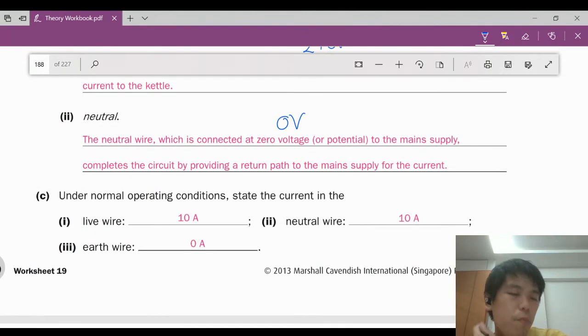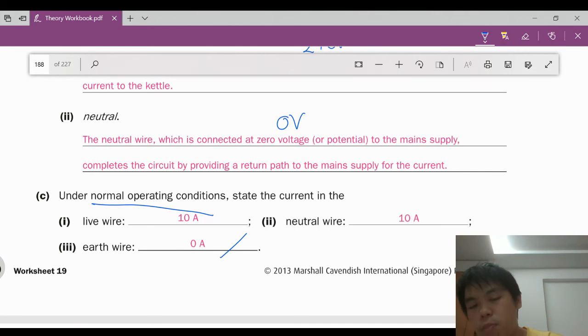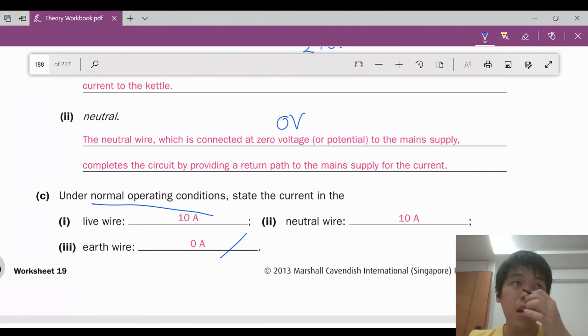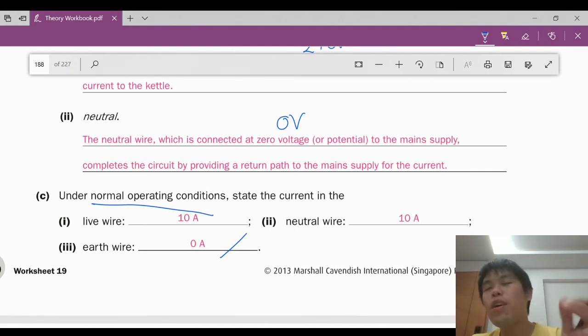Part C: under normal operating conditions, what is the current? If it's operating normally, the earth wire should have zero current, as explained earlier - there should not be any current in the earth wire. If there is current in the earth wire, it means the device is dangerous and may malfunction, and if you touch the metal casing you'll get an electrical shock. The live wire and neutral wire, under normal operating conditions, should have the current flow through the loop - what goes in must come out, like water. If the live wire has 10 amperes, the neutral wire should have 10 amperes also, since it flows through the whole loop. Where is 10 amperes? Down here, it's stated as 10 amperes.